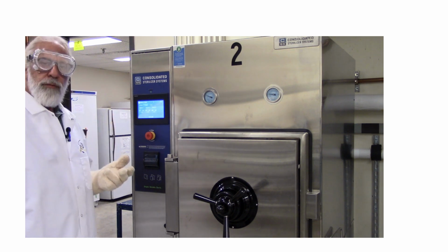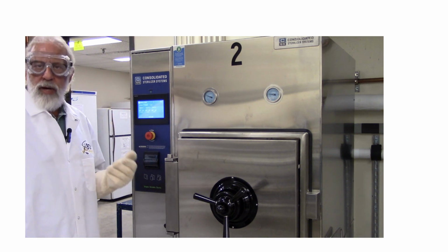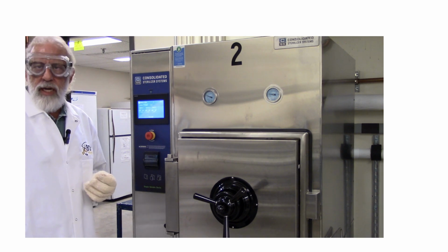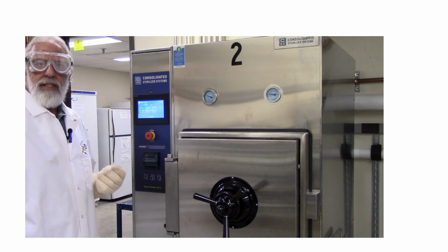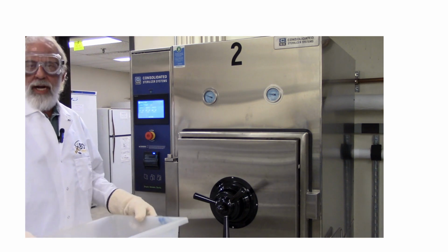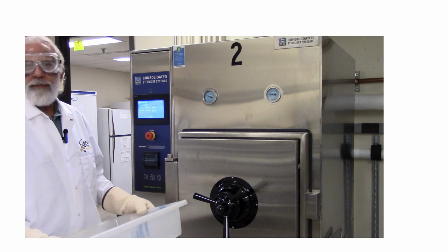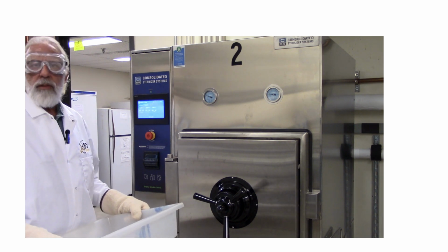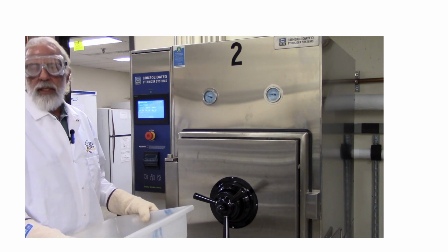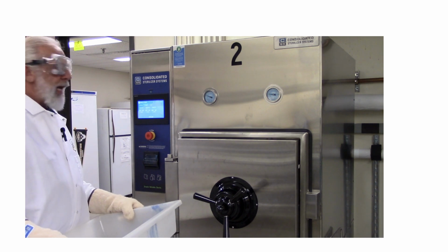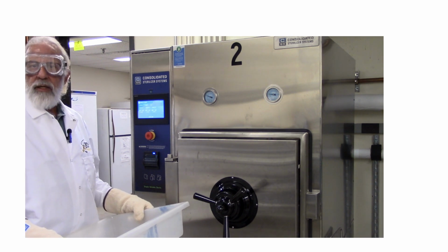You're going to have two choices. The first choice will be between a gravity cycle or a liquid cycle. Gravity cycles are designed for dry goods, glassware, pipette tips, essentially anything without liquid in it. It has a very quick exhaust at the end.